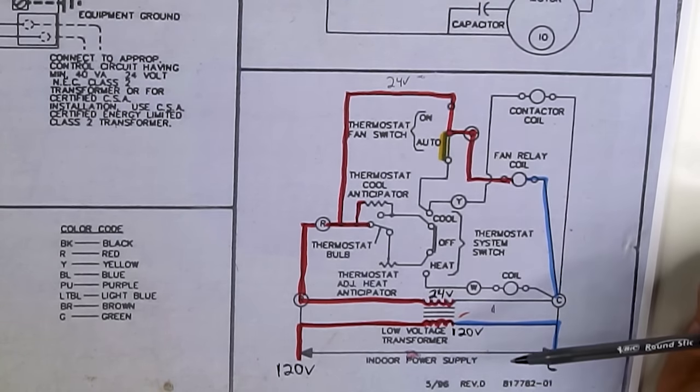There's also a cooling only procedure section spelling out steps like operating the unit at a minimum of 10 minutes before checking charge — you don't want to hook up your gauges right when the unit starts up, you have to allow time for pressures to stabilize. They have a pretty nice legend, well organized, keeping it all in one place, though they don't explain wire colors — but most are self-explanatory: BLK for black, YEL for yellow, BRN for brown. Before looking at the wiring diagram, glance through all of this, read through it, and make sure there are no special notes you're missing.